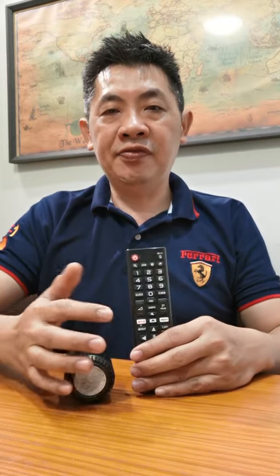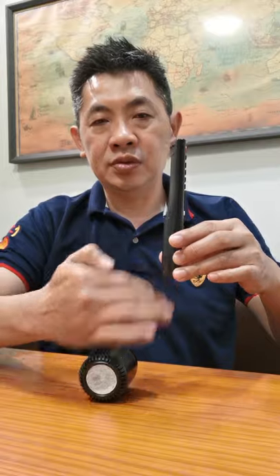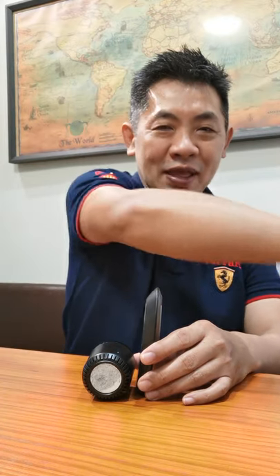In the past, when the fan coil was arranged straight with a fan motor and fins with very big air gaps, after you turned off your aircon the condensate water slowly glided down and drained out through the pipe, then stayed dry — not much problem. Now the fins are smaller and tighter. After you turn off your aircon, water is trapped in the fan coil. To make matters worse, they have shaped the fan coil like an 'A', so if it were 90 degrees, gravity would have a better chance — but in this orientation, less so.